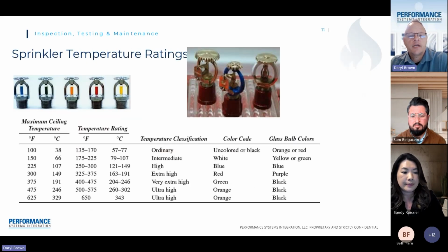Each one of these sprinkler heads, depending on its location, has a designated thermal capacity. That means it's going to operate at a designated temperature rating. In most office buildings, you're going to see them red or green. Sometimes in a commercial setting, you will see higher temperatures. If it's an environment with a higher temperature rating, we definitely don't want that sprinkler head activating at normal temperatures. It's going to need to activate at higher ones.